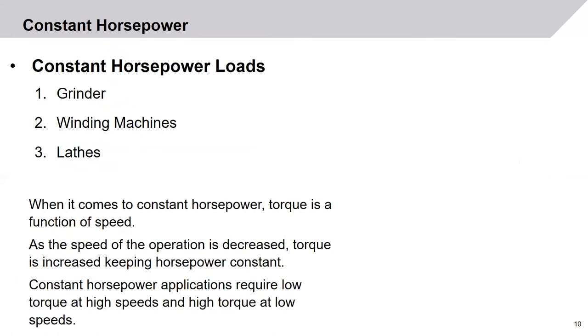Constant horsepower loads include grinders, winding machines, and lathes. When it comes to constant horsepower loads, torque is a function of speed: as the speed of the operation is decreased, torque is increased, keeping horsepower constant. Constant horsepower applications require low torque at high speeds and high torque at low speeds.